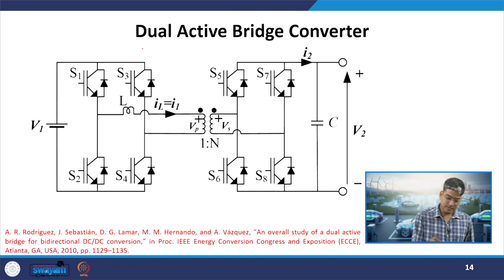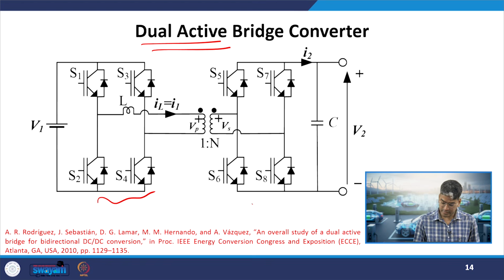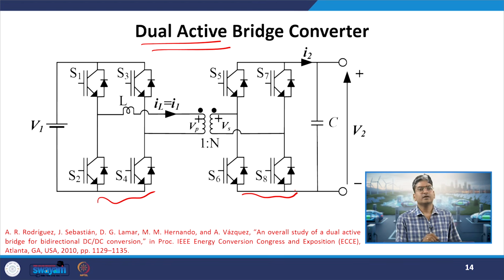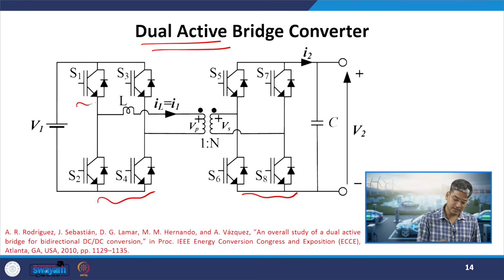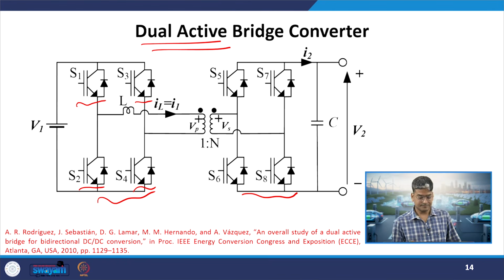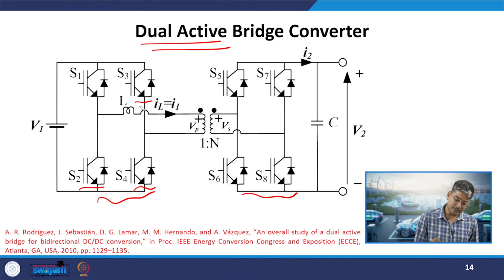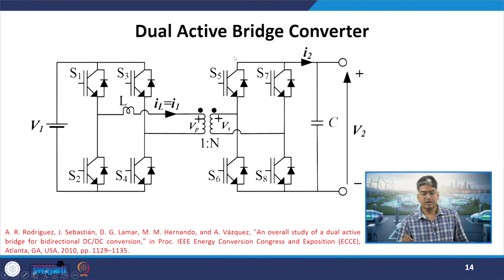Why is it called dual active bridge? It has two bridges, one on the primary side and one on the secondary side, constructed using active devices. These are fully controlled devices; here we consider IGBTs, but the working remains the same even if designed using MOSFETs. Any fully controlled device makes the DAB operation the same whether realized using IGBT or MOSFET. So how do I decide whether to go with IGBT or MOSFET?